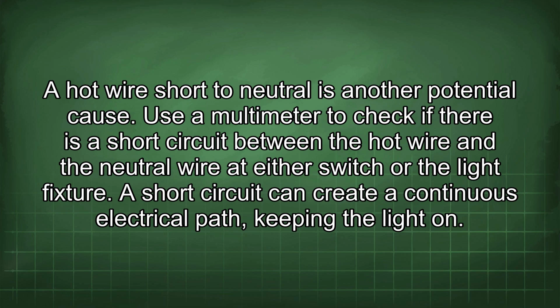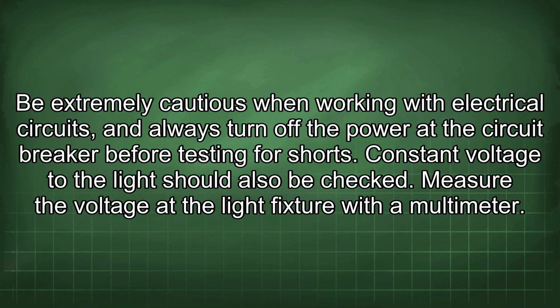A hot wire short to neutral is another potential cause. Use a multimeter to check if there is a short circuit between the hot wire and the neutral wire at either switch or the light fixture. A short circuit can create a continuous electrical path, keeping the light on. Be extremely cautious when working with electrical circuits, and always turn off the power at the circuit breaker before testing for shorts. Constant voltage to the light should also be checked.